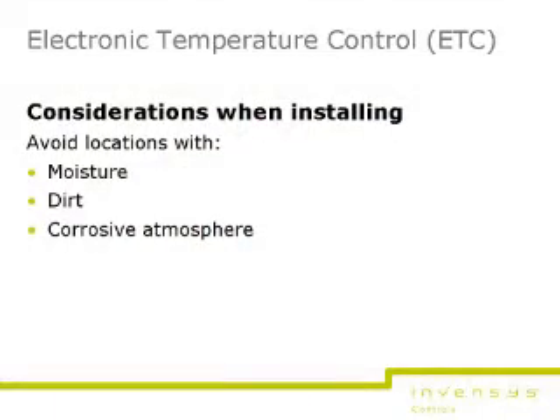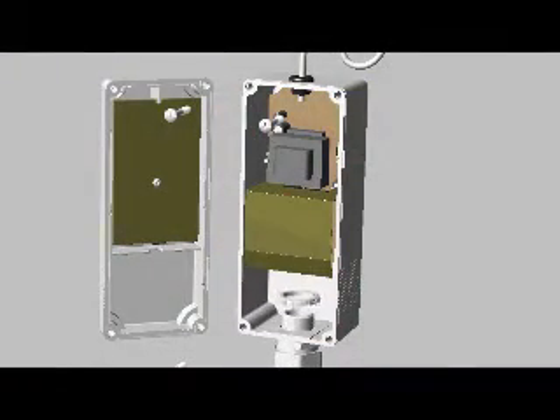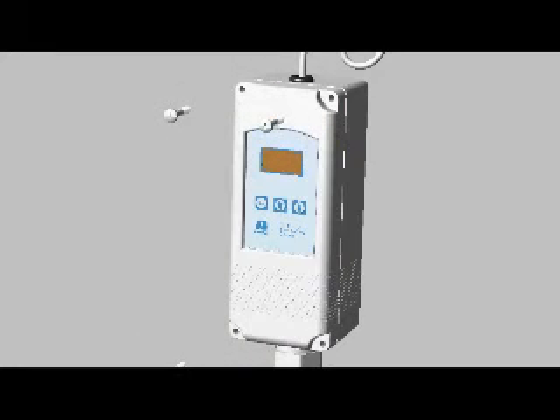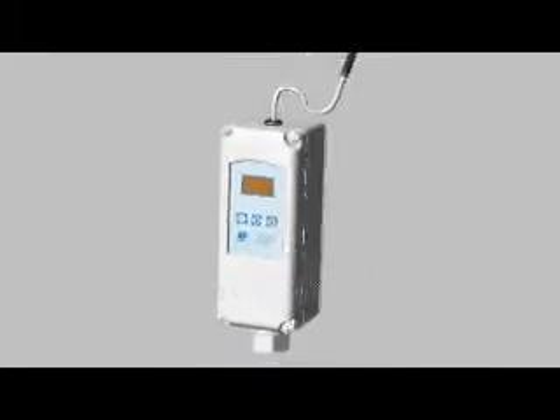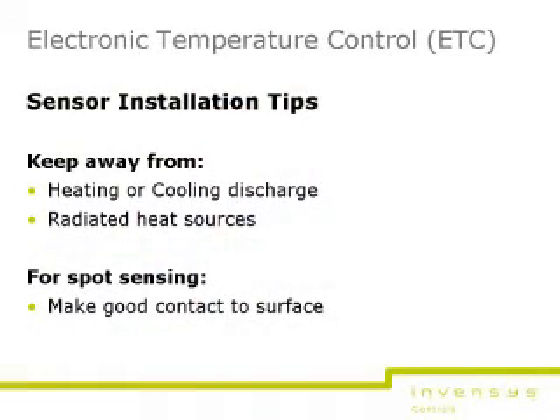2. The control components are not position sensitive, but should be mounted where they can be easily wired and adjusted. 3. Avoid excess conditions such as moisture, dirt, and corrosive atmospheres. 4. The ETC has two provisions for half-inch diameter holes on the back or the bottom, depending on installation preference. 5. The conduit hub should be secured prior to securing the plastic housing of the control. 6. Next, mount the sensor. 7. The sensor should be mounted where it will not be affected by heating or cooling discharge or radiated heat sources. For spot sensing, the sensor should be in good contact with the surface being sensed.